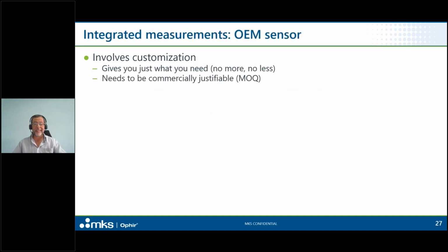A specific but very common answer to steps 2 and 3 is to have an integrated measurement capability by way of an OEM sensor built into the host system. Laser-based surgical systems, for example, generally have a regulatory requirement to have an integrated measurement capability. The advantage of this sort of OEM sensor is that it gives you exactly what you need. It's tailored to your conditions, your wavelength, your power level, and so on.